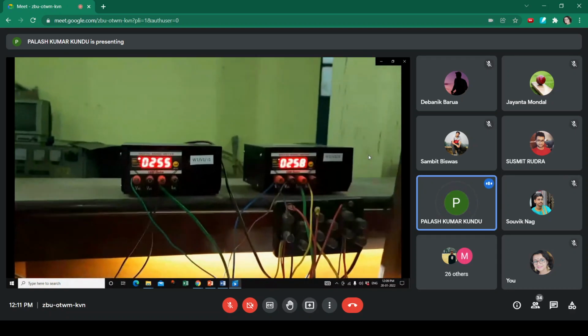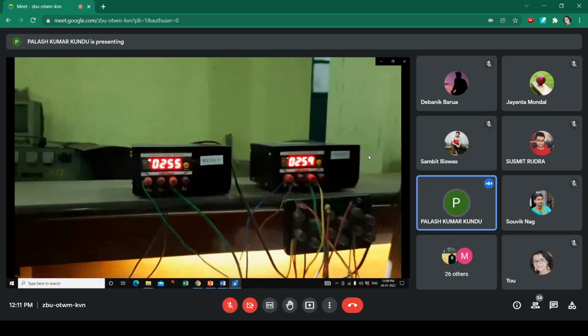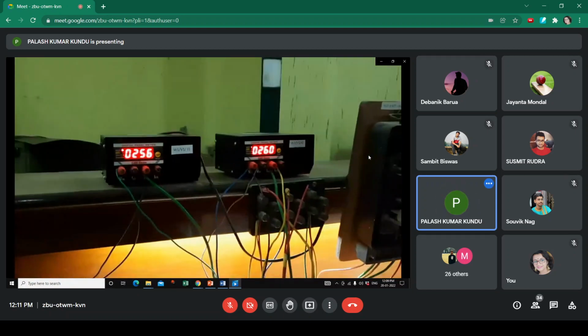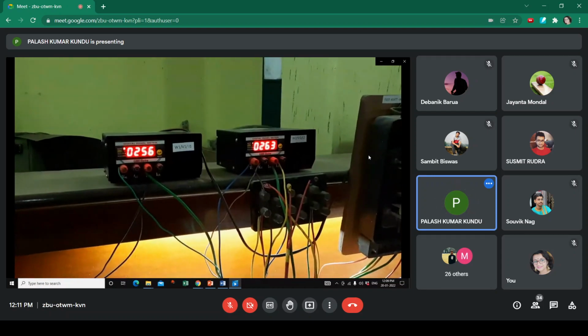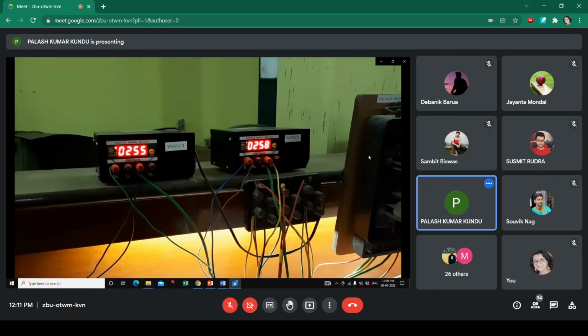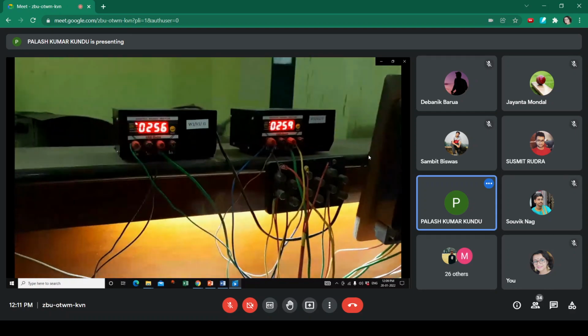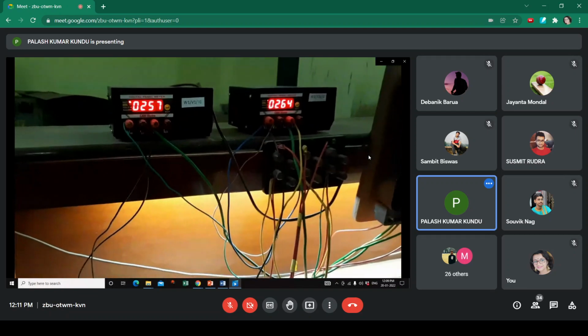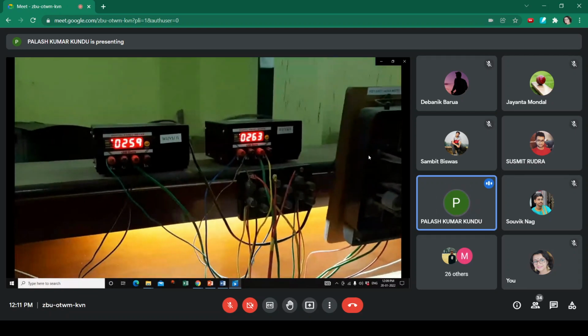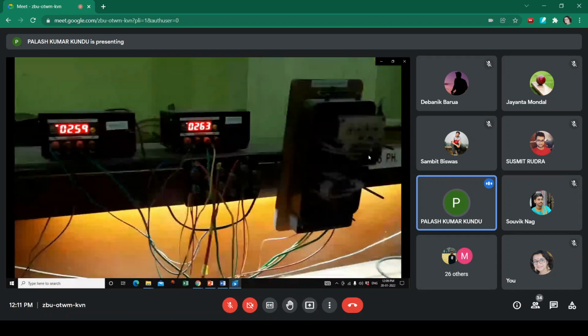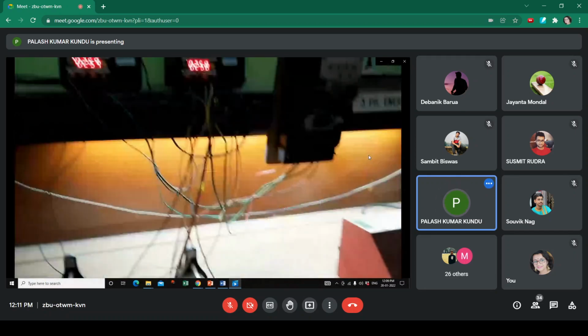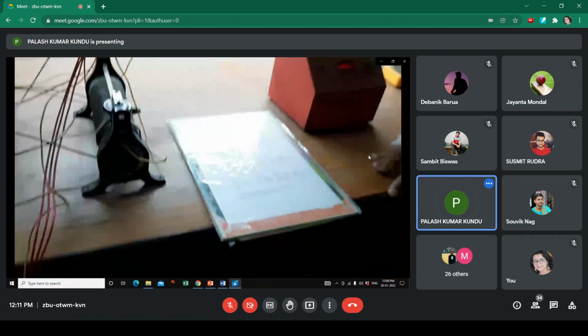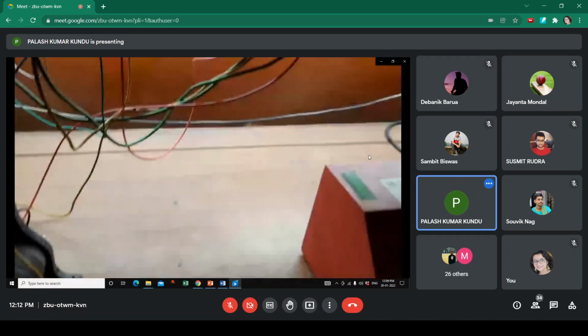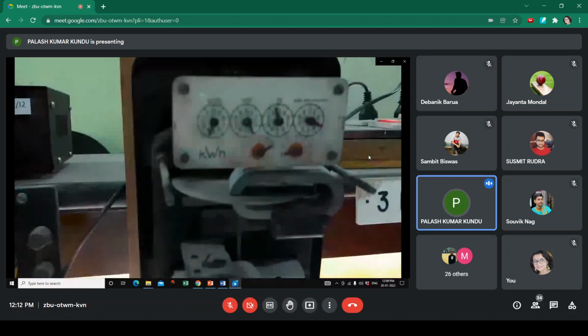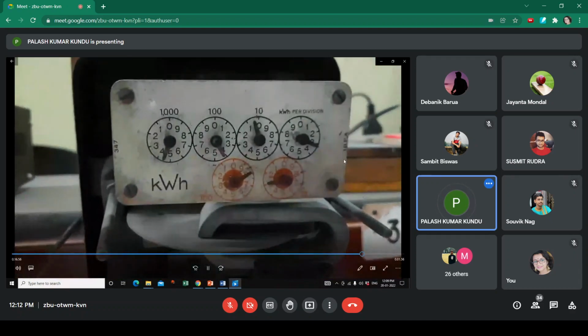You can see the wattmeters make the same reading. Same. Now you can see it is showing the same reading. So it is proper reading. And now in run 2, it's a long run. So we'll check the dial reading of this energy for 30 minutes. So we will run it for 30 minutes.